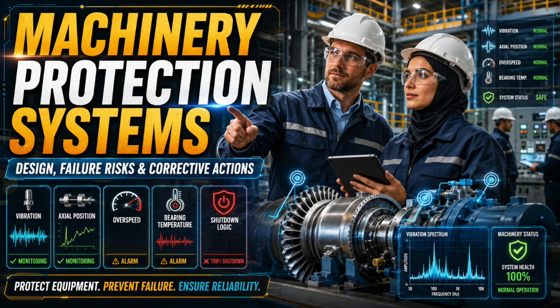Now let me make this highly practical for you. When you review a machinery protection package, do not only check tag numbers, check the failure mode. Why is this channel required? What does it protect? Where is the sensor located? What surface is it measuring? How is it mounted? What is the cable route? Where is the shield grounded? What is the monitor range? What are alarm and shutdown set points? Is voting logic defined? Is time delay defined? Are bypasses controlled? Are relays normally energized or de-energized as intended?